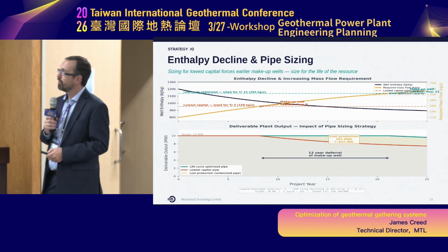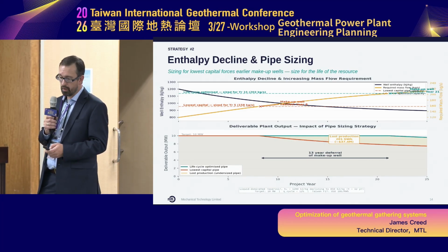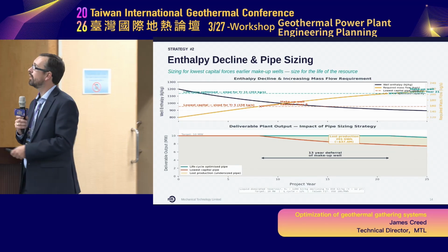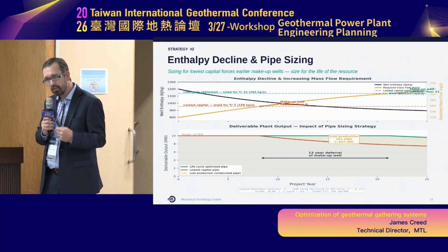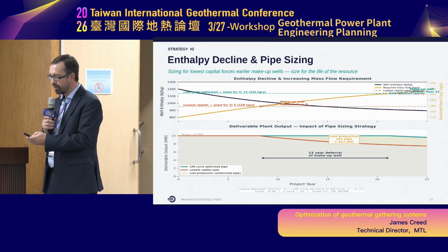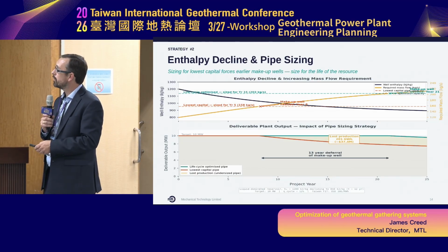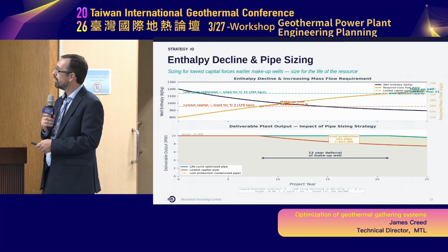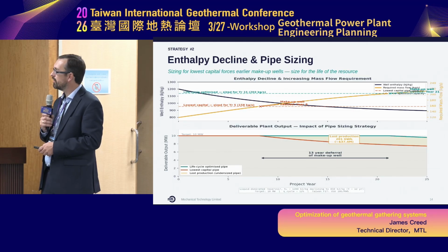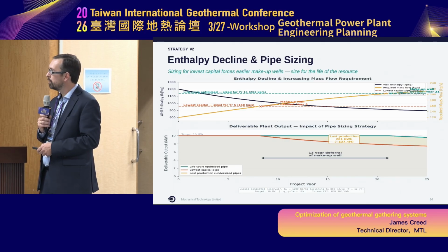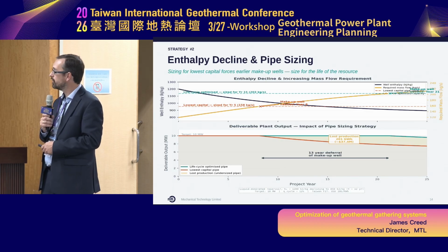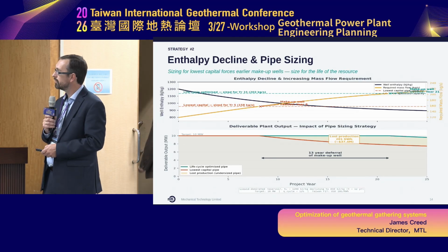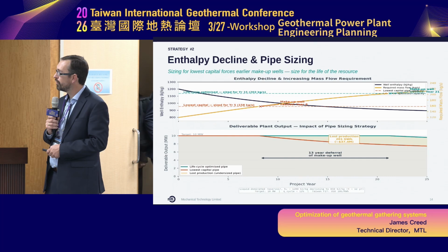This graph demonstrates the need to correctly size your pipelines. Over time, enthalpy declines, so you get less heat and less power. You can pick the lowest capital cost option, but if you pick an optimal pipe size instead, you can extend the point before you need to drill make-up wells. In this graph, that's 13 years, so you're deferring your make-up wells and deferring that capital cost.